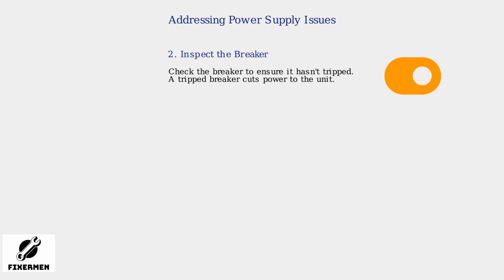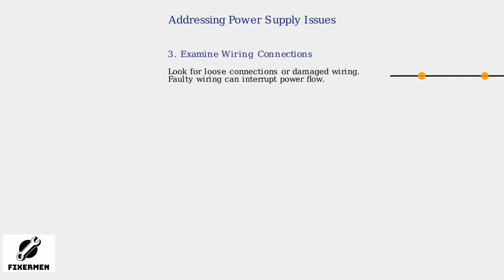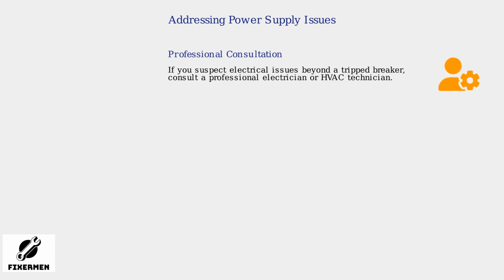The first step in addressing power supply issues is to confirm that the AC unit is receiving the correct voltage supply of 208-230 volts AC. A voltage drop can prevent the fan from starting, so testing this is crucial. Next, inspect the circuit breaker to make sure it hasn't tripped. A tripped breaker will cut power to the entire unit, causing the fan to stop spinning. Finally, examine the wiring for any loose connections or visible damage. Faulty wiring can interrupt the power flow to the fan motor, preventing it from operating properly. If the issue appears to be more complex electrical problems beyond a simple tripped breaker, it's important to consult a professional electrician or HVAC technician for safe and proper diagnosis.